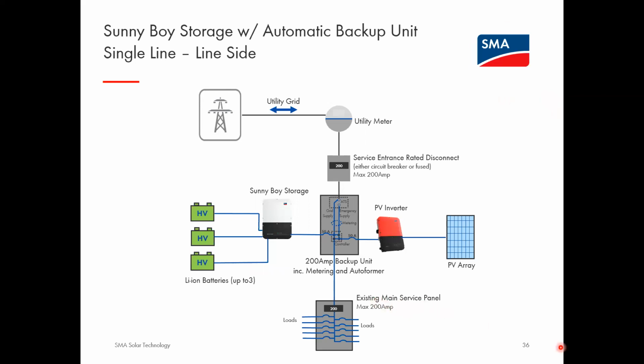So one of the easiest ways to integrate the automatic backup unit in this scenario is to connect it to the line side of the main breaker, basically below the service entrance rated disconnect. When the grid is available, the automatic backup unit just acts as a pass-through, passing the flow of power from the utility to and from the loads in the main service panel, and the PV inverter is capable of injecting power, feeding back into the utility grid.